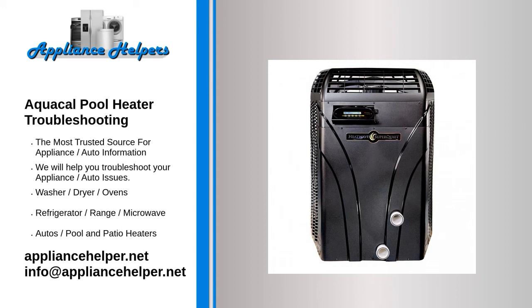Examine power sources. If you do not see an error message and instead, your pool heater just shuts off immediately after or shortly after turning it on, then this can be an indication of a power issue. In this case, you will want to check your power sources and connections to make sure everything is as it should be. Checking the breaker, resetting the unit, and going over connections is the step you will want to take.